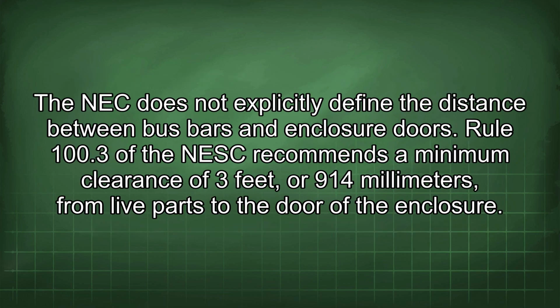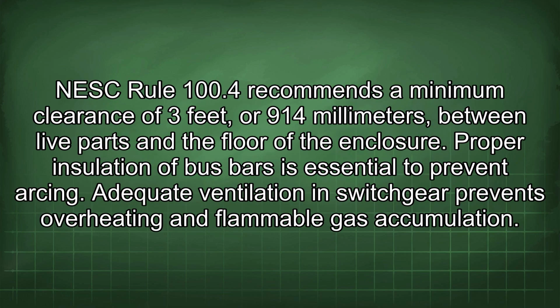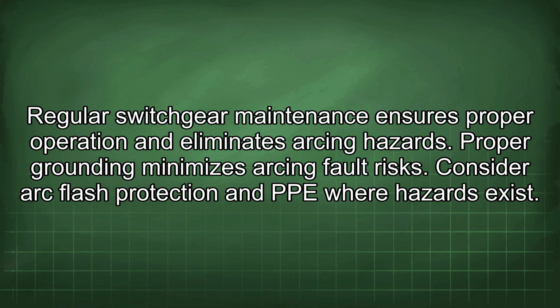The NEC does not explicitly define the distance between bus bars and enclosure doors. Rule 100.3 of the NESC recommends a minimum clearance of 3 feet, or 914 millimeters, from live parts to the door of the enclosure. NESC Rule 100.4 recommends a minimum clearance of 3 feet, or 914 millimeters, between live parts and the floor of the enclosure. Proper insulation of bus bars is essential to prevent arcing. Adequate ventilation in switchgear prevents overheating and flammable gas accumulation. Regular switchgear maintenance ensures proper operation and eliminates arcing hazards. Proper grounding minimizes arcing fault risks. Consider arc flash protection and PPE where hazards exist.